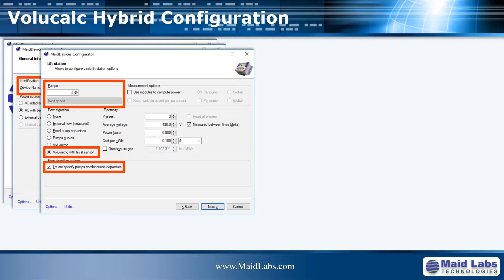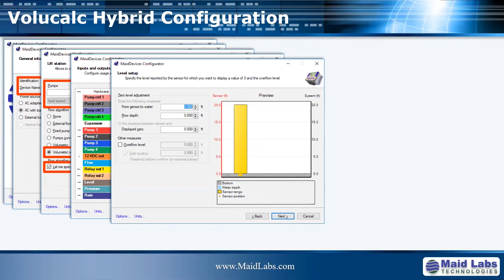You specify the name of the station, whether you have a cellular modem, the number of pumps, how you will calculate flow, and if you want to enter pump capacities. Then the size of the current sensors, the settings for the level sensor and pressure tap if you're pumping into a pressure line and want to record it. If you have an overflow pipe, the instrument is an open channel flow meter with about 10 different formulas, so you can specify the level of the overflow pipe, its diameter, and so on.